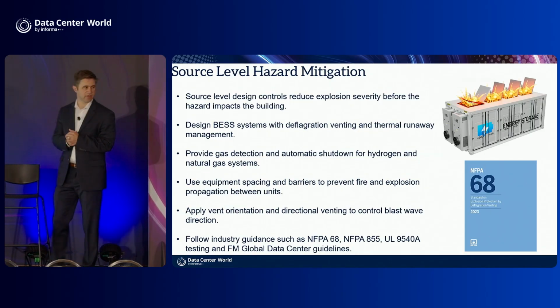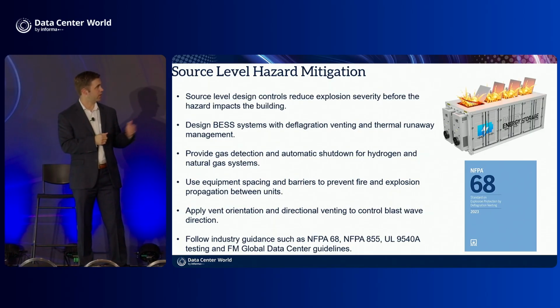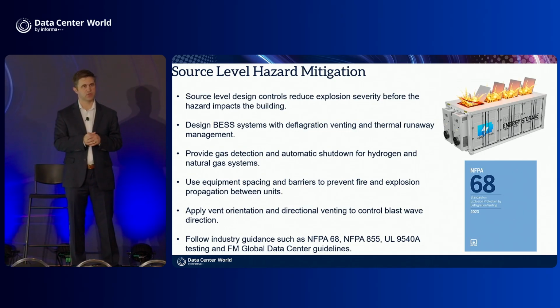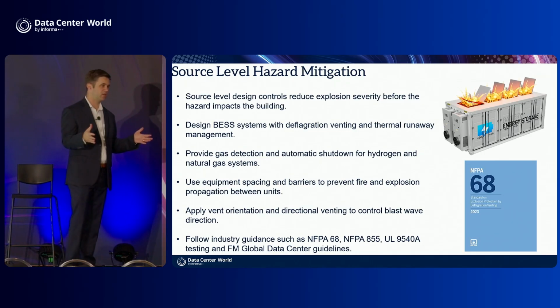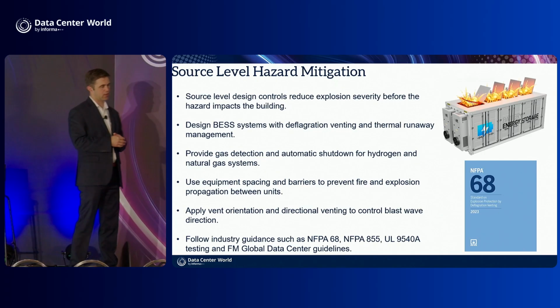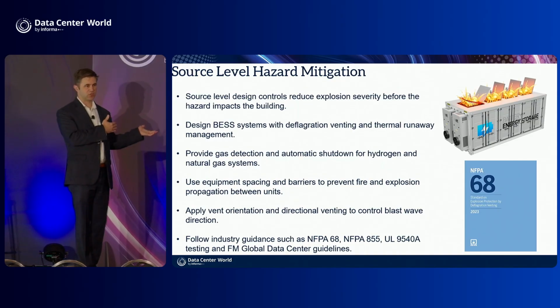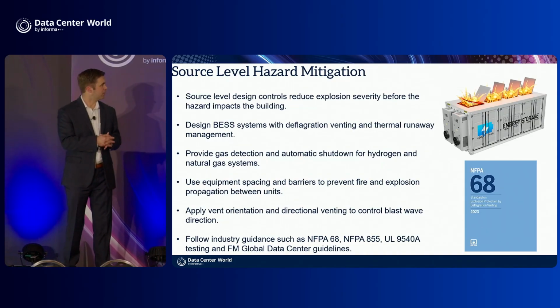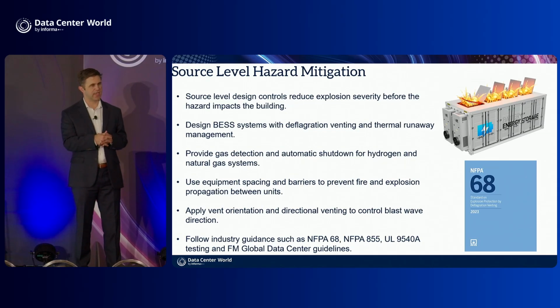Most BESS containers now are equipped with deflagration vent panels to relieve pressure inside the container before that disastrous scenario we showed in the earlier video occurs. These are source-level mitigation measures that reduce either the consequence or the frequency of the event occurring.